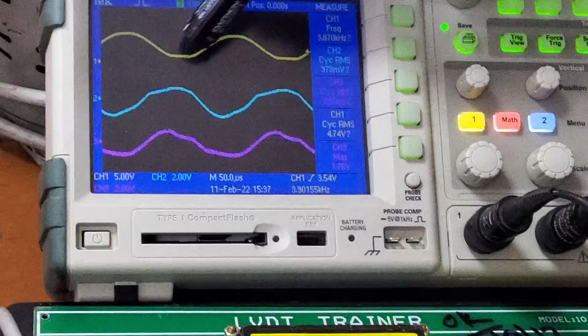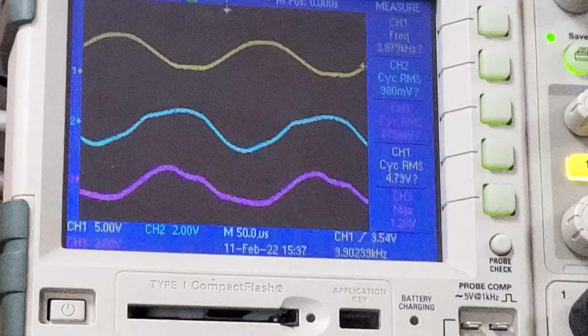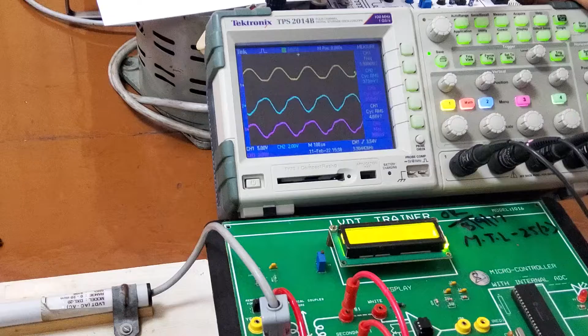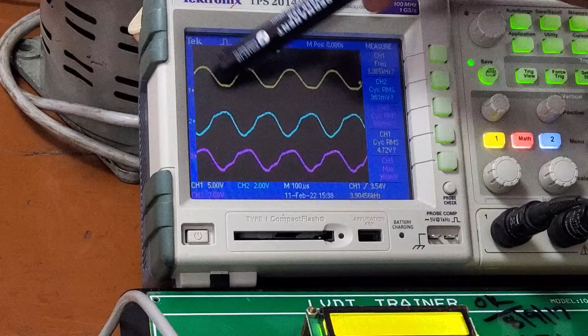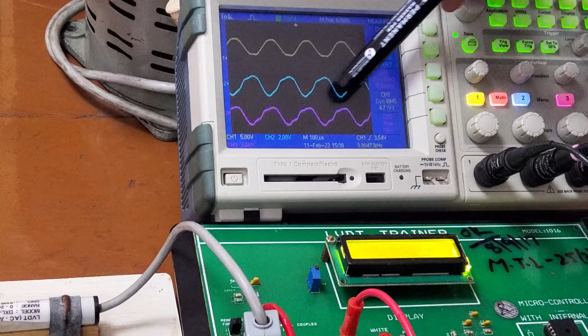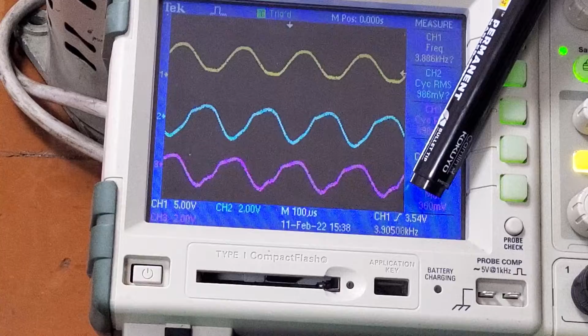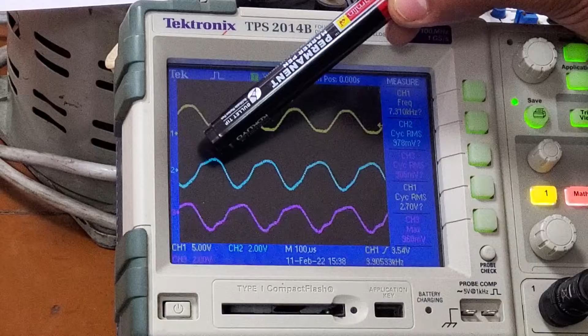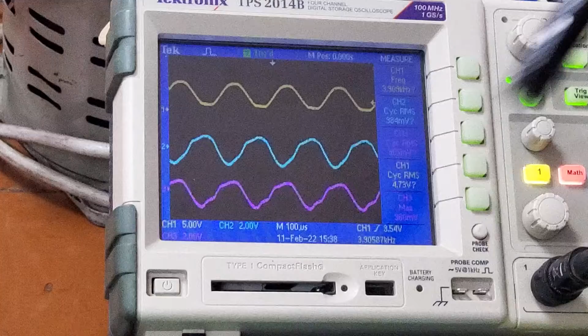So here you see your primary winding input waveform, and you get an ES1 and ES2 waveform. This is the primary input voltage to the primary coil of the LVDT. The blue one is your ES1 voltage, and the purple is your ES2 induced output voltage through the secondary coil. Both waveforms are 180-degree phase shifted, so when one is at peak, the other is down, and vice versa.